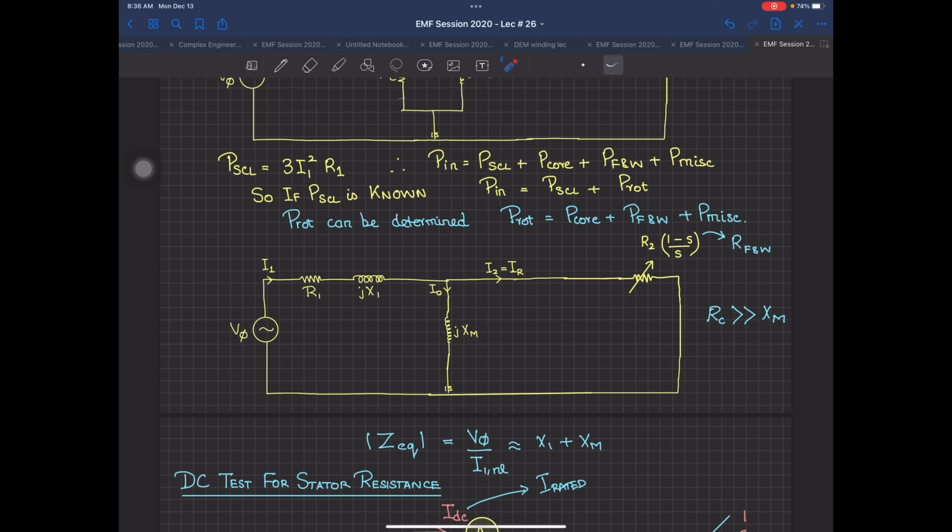Yes, you can come in, you can do it. But normally, especially if you are in Pakistan, and if you are purchasing a motor, it's rare that your current waveform is sinusoidal, very rare. For a small motor of 500-600 watts, 1 horsepower, then certainly it is possible. But if you are talking about 2, 3 and 4 horsepower, the current waveform is very difficult. It is always going to have some distortion like this, or maybe sometimes the voltage waveform is like this. One type of waveform is this also, a third harmonic waveform, which is also possible sometimes inside the machine.